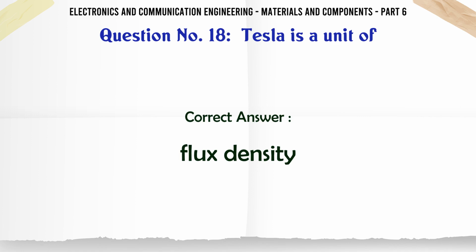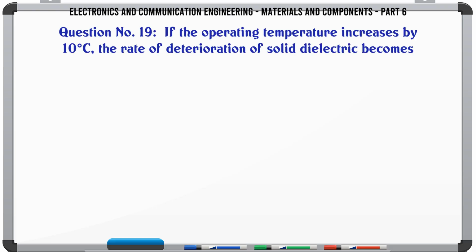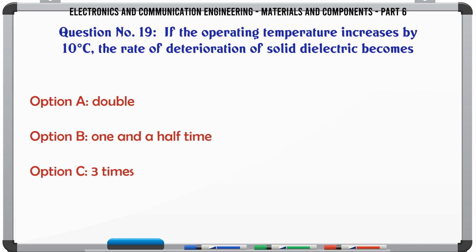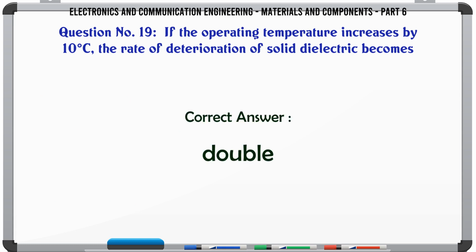If the operating temperature increases by 10 °C, the rate of deterioration of solid dielectric becomes A. double, B. 1.5 times, C. 3 times, D. 4 times. The correct answer is double.